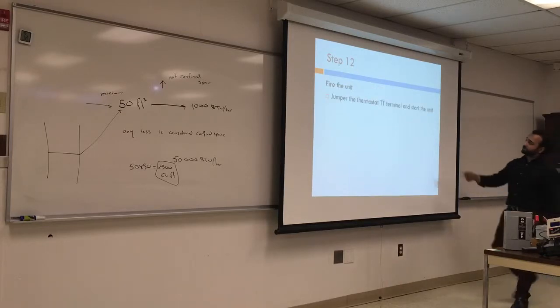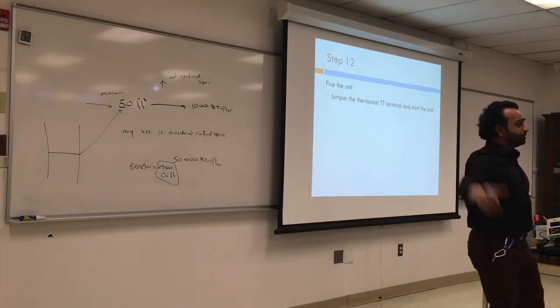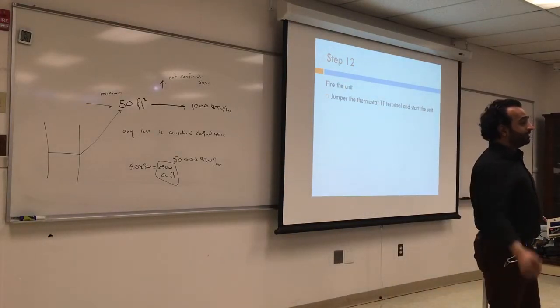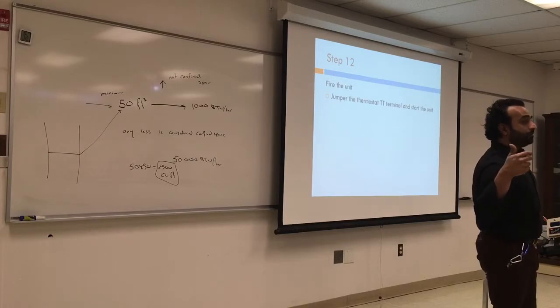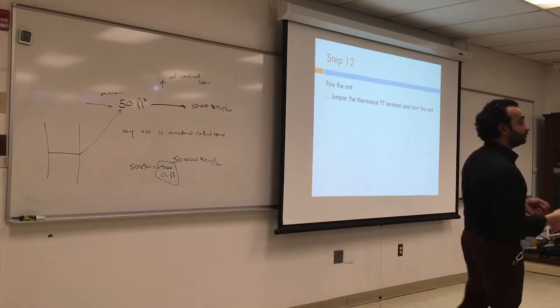Fire the unit, jumping the thermostat. Over here, the thermostat is right next to you. In real life, the thermostat will be on the second or first floor. So to shortcut the distance so you don't go up and down, you can jump the thermostat either in the cad cell primary control or in the aquastat, and it should turn on. Put a jumper and turn it on, and it should turn on.